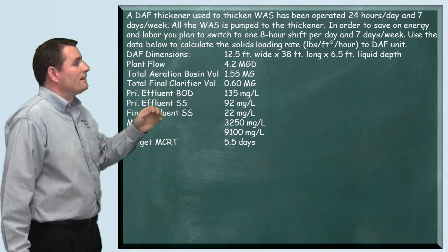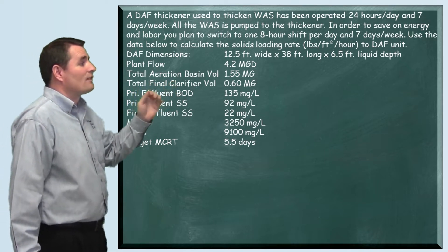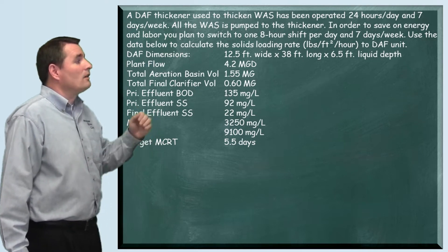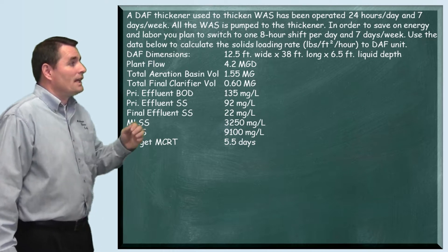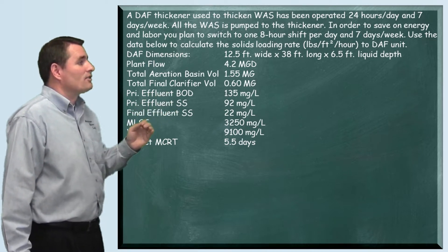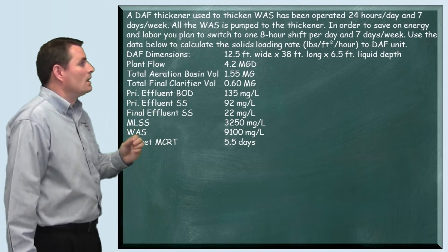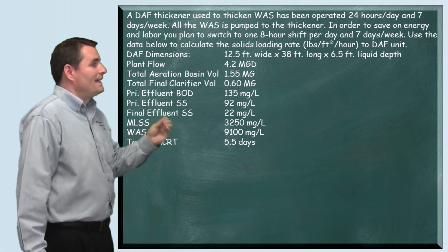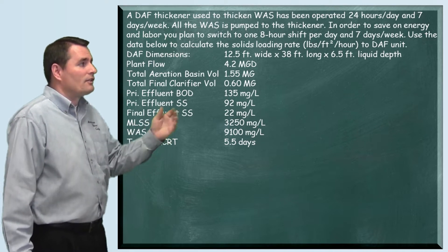The problem reads: a DAF thickener used to thicken waste activated sludge has been operated 24 hours a day, seven days a week. All of the waste activated sludge is pumped to the thickener. In order to save energy and labor, you plan to switch to one eight-hour shift per day, seven days a week. Use the data below to calculate the solids loading rate in pounds per square foot per hour to the DAF unit.